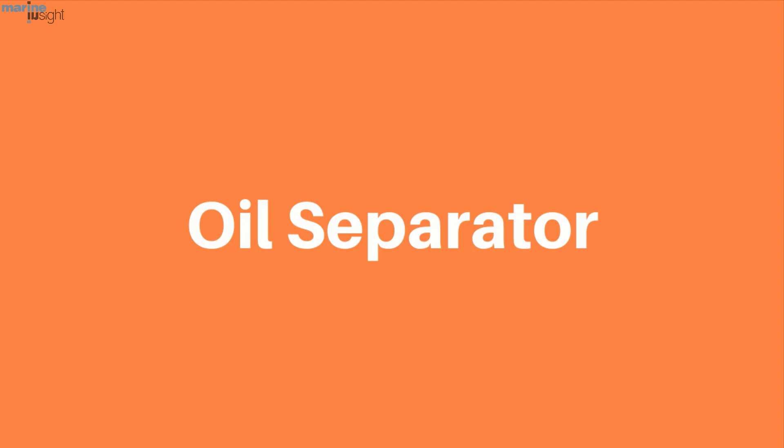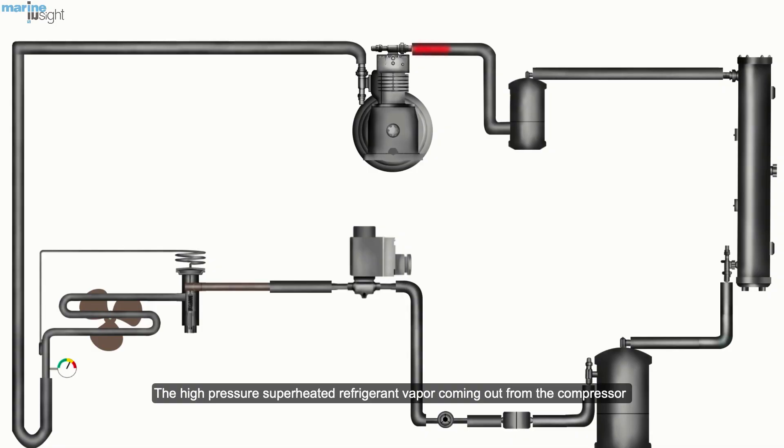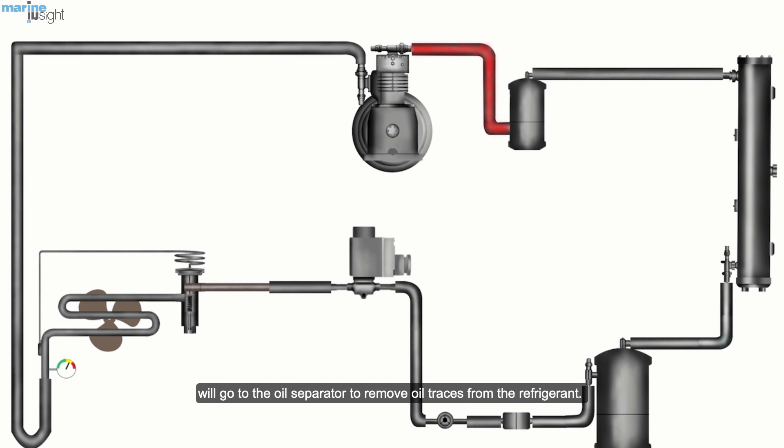Oil Separator. The high pressure superheated refrigerant vapor coming out of the compressor will go to the oil separator to remove oil traces from the refrigerant. An oil separator ensures oil return to the compressor oil sump.